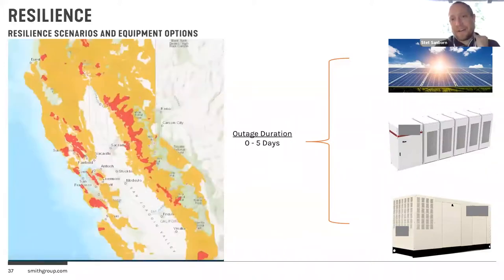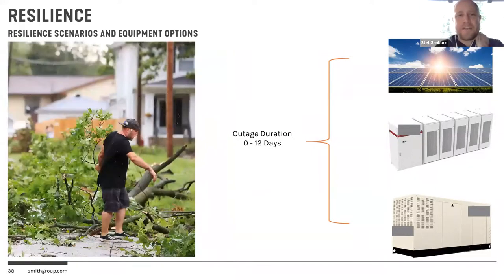When we're targeting resilience, we typically look for four to five days of backup because that's typically what we see when the grid goes down. Take my parents: this summer, the derecho wind event came through Marshalltown, in the middle of Iowa, and my parents didn't have power for 12 days. I will admit I purchased a generator for them and had it shipped overnight because I couldn't find anyone who could do battery solar in Marshalltown, Iowa, but we're working on the microgrid for them.